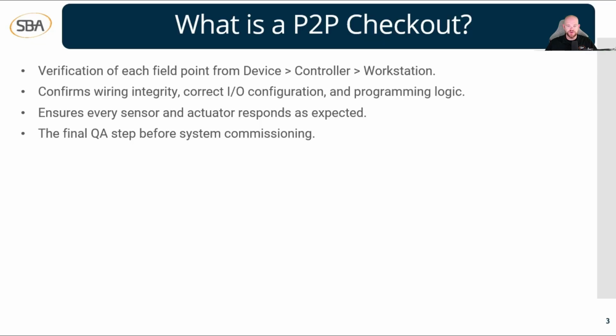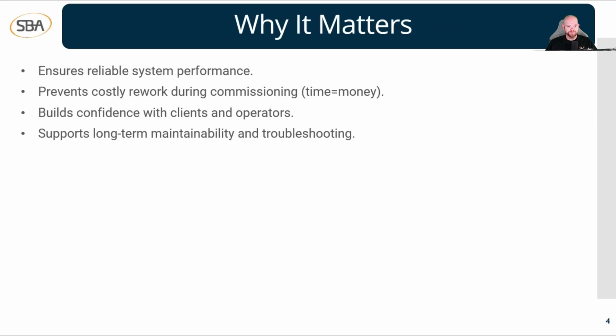One little note here at the end. This is the final note for this slide: point-to-point checkouts are the final quality assurance step before we get to system commissioning. Making sure that we do the point-to-point checkout correctly and very thoroughly can really help us when we get to the commissioning process. So we really have to make sure we have this lined out correctly and have all these steps worked out, so that it's a little bit easier on us when we get to commissioning. So that is what a point-to-point checkout is.